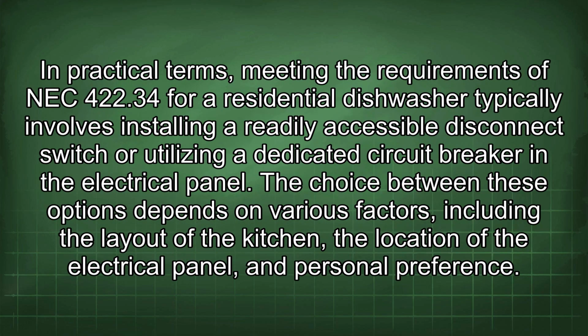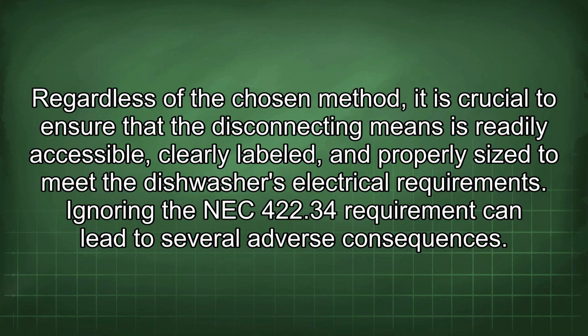In practical terms, meeting the requirements of NEC 422.34 for a residential dishwasher typically involves installing a readily accessible disconnect switch or utilizing a dedicated circuit breaker in the electrical panel. The choice between these options depends on various factors, including the layout of the kitchen, the location of the electrical panel, and personal preference. Regardless of the chosen method, it is crucial to ensure that the disconnecting means is readily accessible, clearly labeled, and properly sized to meet the dishwasher's electrical requirements.